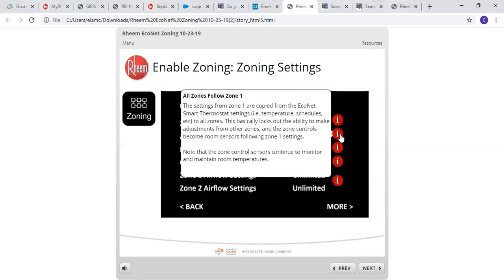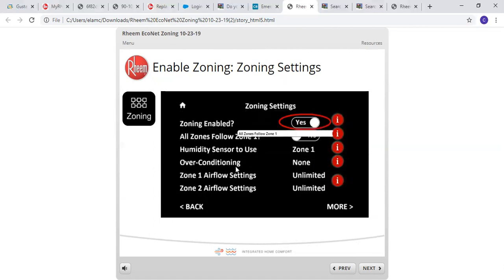All zones follow Zone 1. This setting from zone 1 is copied from the Econet smart thermostat to all the zones. This basically locks out the ability to make adjustments from other zones and zone controls. They just become room sensors, basically, and they follow Zone 1 settings. Note that the zone control sensors continue to monitor and maintain room temperatures.